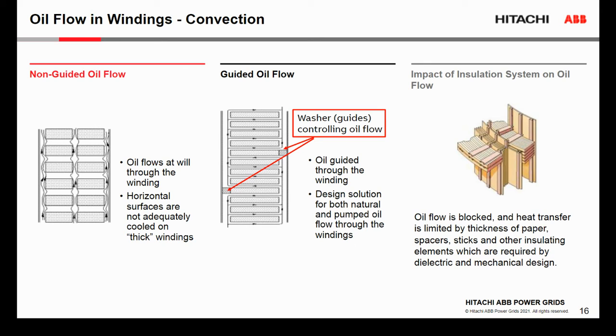But in the design, we always have to make sure that when we design the insulation system, we consider the reduction of the cooling surface area in the parts of the windings covered by the spacers, by the axial ribs. And also we have to make sure that the oil is not restricted by the insulation parts.